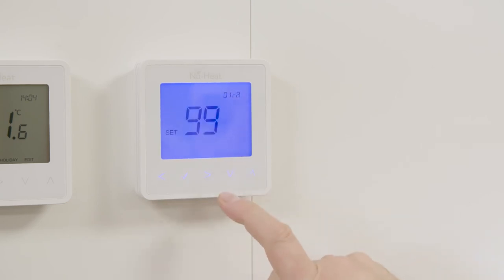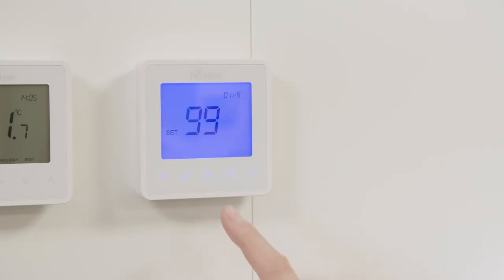Use the up and the down keys to set the large digits to the board address of the UH8 RF wiring centre. This is the number that is set on the UH8 RF switches. You must use a unique board address for each of the wiring centres installed. Press tick once.